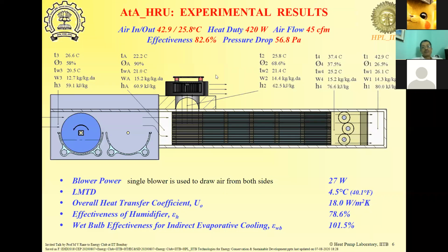Okay. Now, this particular air-to-air heat recovery system, which is described here, is tested to cool air from 42.9 degrees centigrade to 25.8 degrees centigrade in a single pass in this case. The flow rate in this particular case was about 45 CFM. It is modular. So if you just double the size of the heat exchanger, put twice the number of core elements, you will have twice the flow rate. The effectiveness was quite high, 82.6%. The pressure drop was quite low, just 5.6 mm of water column or 56, 57 pascals.